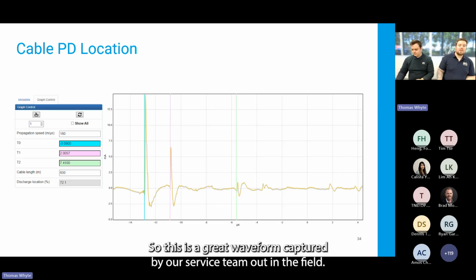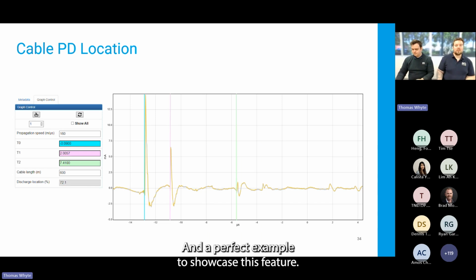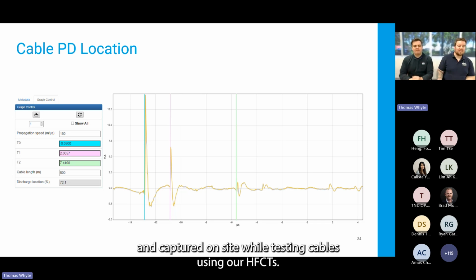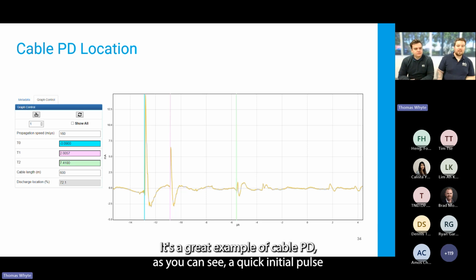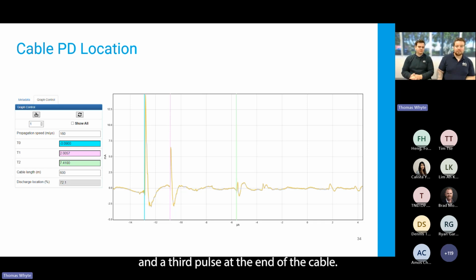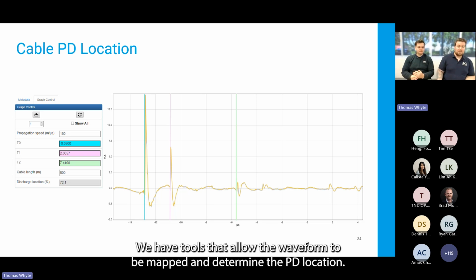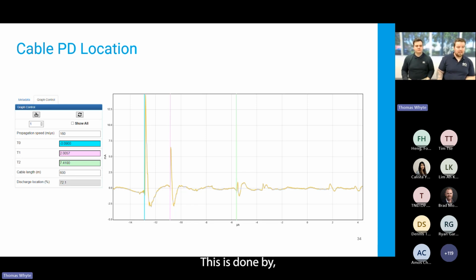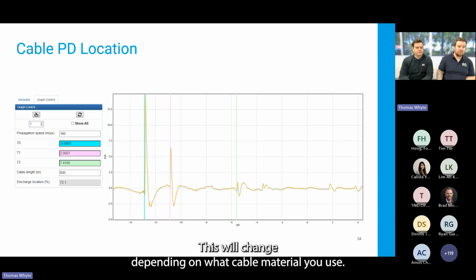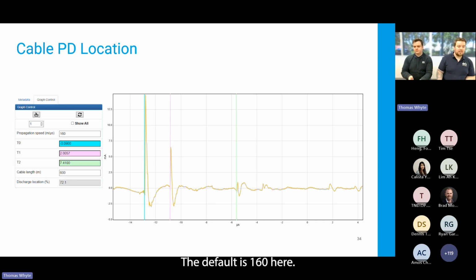So this is a great waveform captured by our service team out in the field and a perfect example to showcase this feature. Here we have a waveform generated by the Plus² and captured on site while testing cables using our HFCT accessory. It's a great example of cable PD. As you can see, a quick initial pulse here, a secondary pulse with slightly lower amplitude, and a third pulse at the end of the cable. When analyzing the data on a computer, we have tools that allow the waveform to be mapped and determine the PD location. This is done by inputting the propagation speed of the cable. This will change depending on what cable material you use. The default is 160 here. The cable length, in this case, is 600 meters.